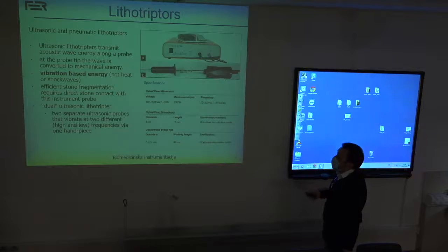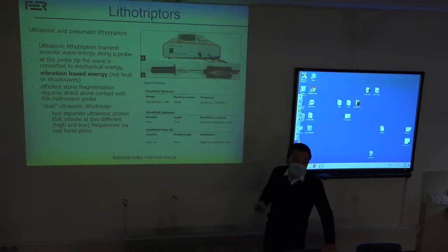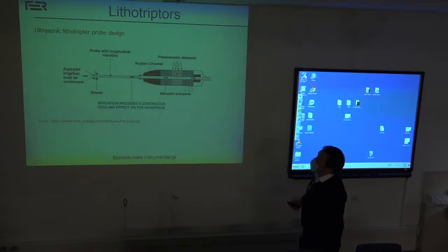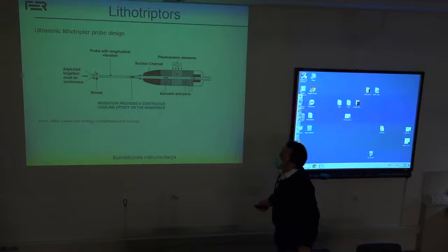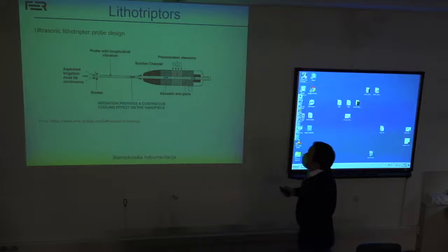If you remember, we had the electrosurgical devices where the output power was declared up to 1 kilowatt. So this is much smaller energy. So this is a more technical, so to say, description of the lithotripsy probe. So the acoustic part, so to say, is actually here.